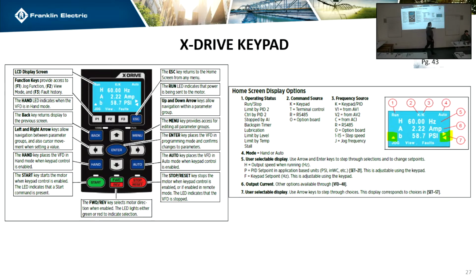Number 4 up here will tell you if it's in hand or auto. Number 5 is user selectable, but by default it's going to be your speed. You can go between H, which is the output speed, P, which is the PID set point, or F, which is the hertz set point. You'll see these little arrows. They should be highlighted on your top row right now. If you hit left and right, this will change between H and F. F is telling you what the set point is for the speed. H is telling you what it's really doing. So all the H's should be 0 right now. The F's are going to be all over the place.